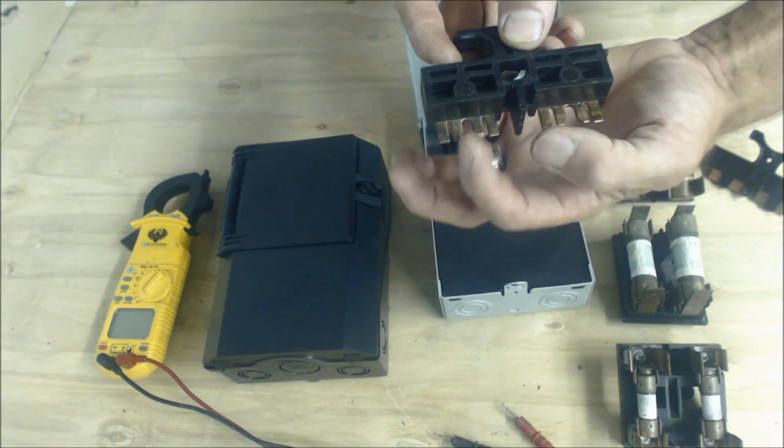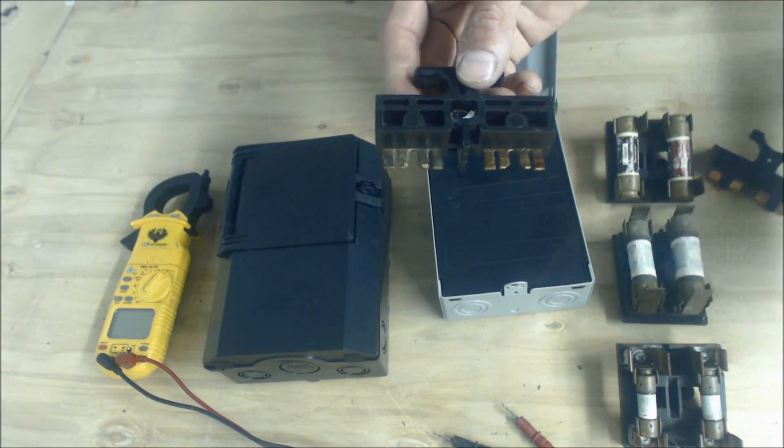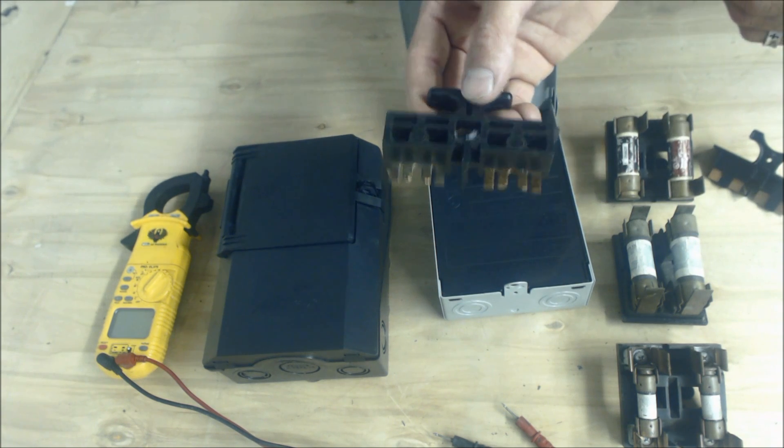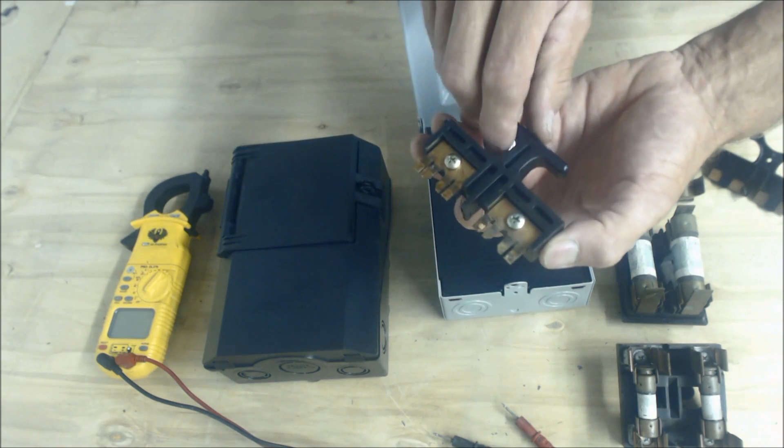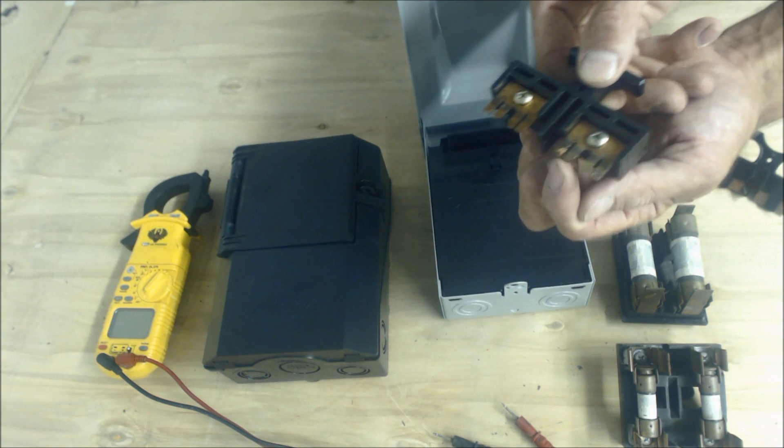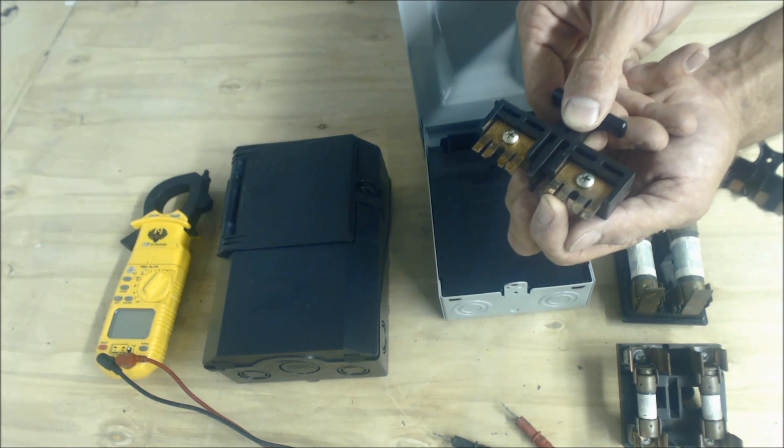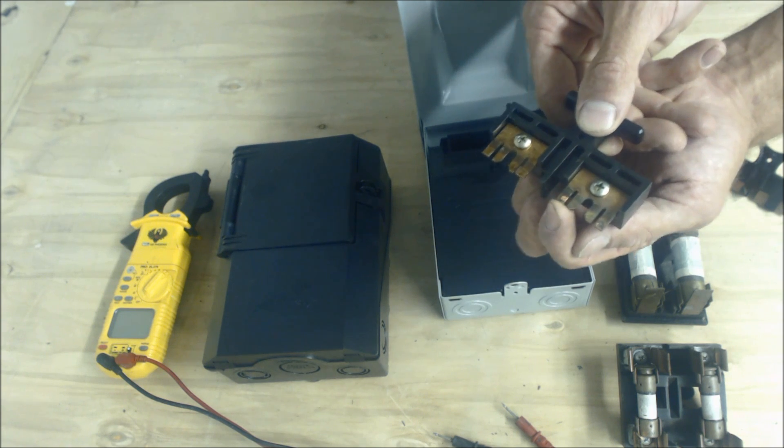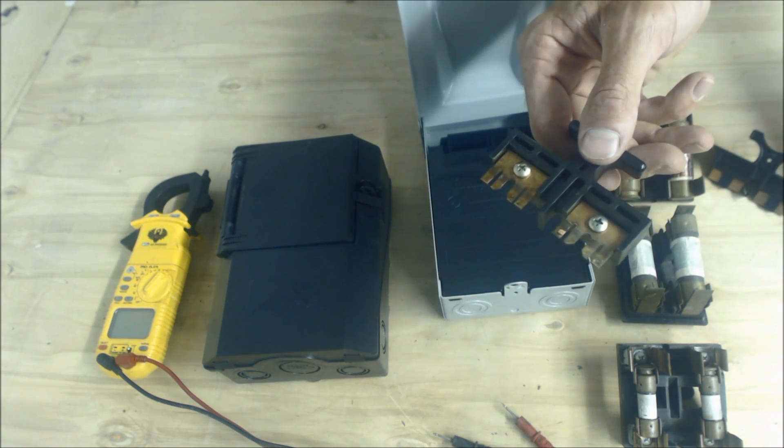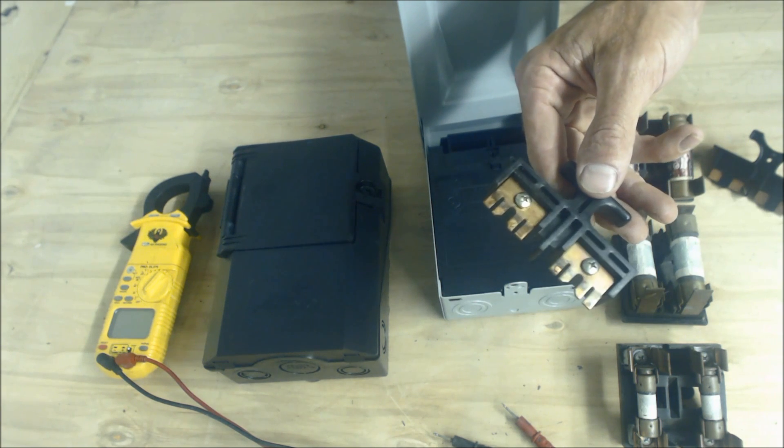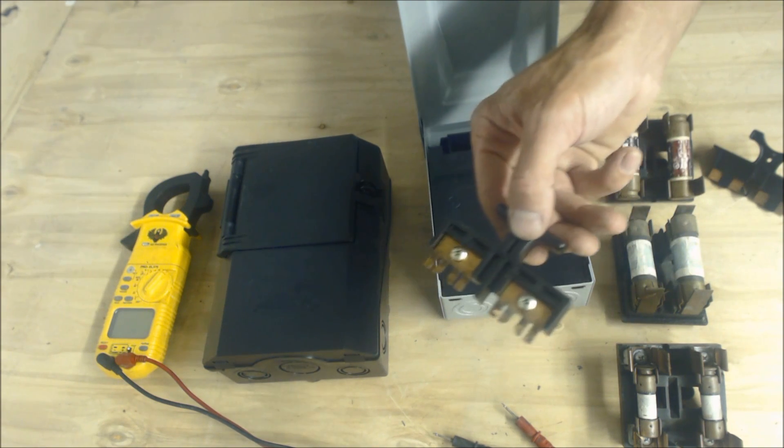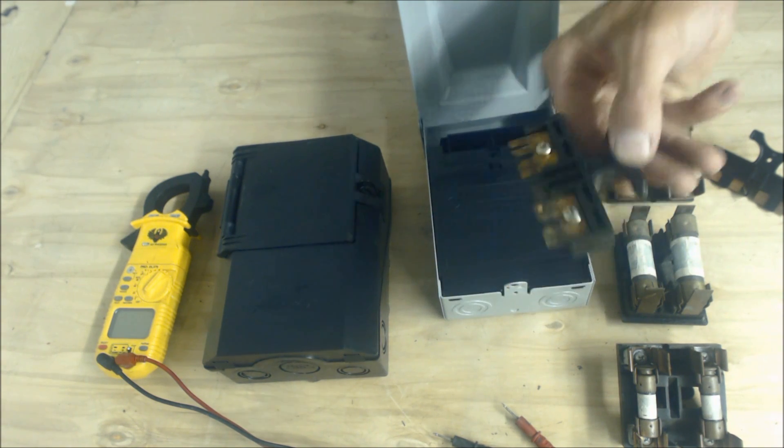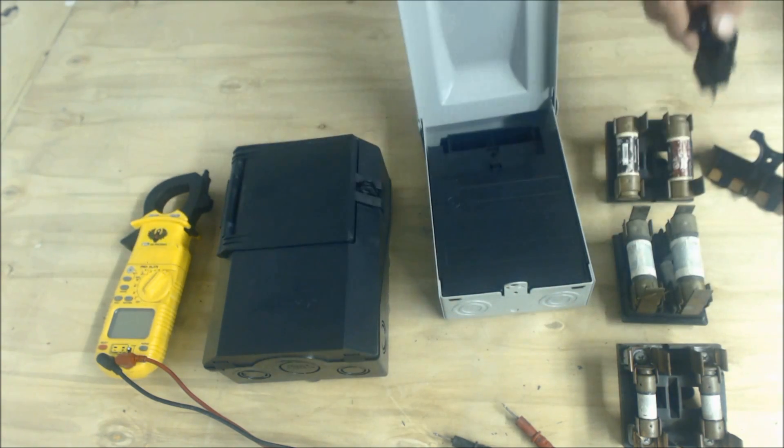But I'm not so concerned just about this, I'm more concerned about the compressor. So the actual compressor, I slide this in and then I tap it in, just to make a good solid electrical connection, just like you're turning on a switch. Instead of it sparking and coming in, making contact, turning on the compressor for about a quarter second or something, pulling it off and pushing it back in again, that can cause the compressor to go out on a high limit, high amperage. And then when you finally do get it in, your condenser fan turns on, but your compressor does not.